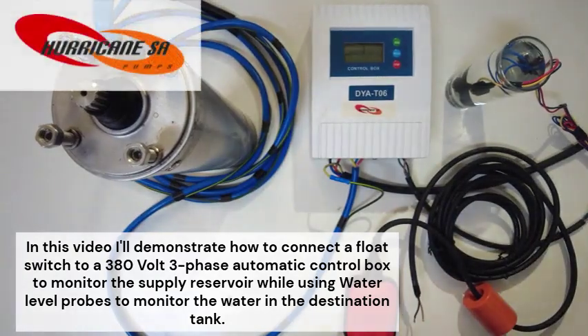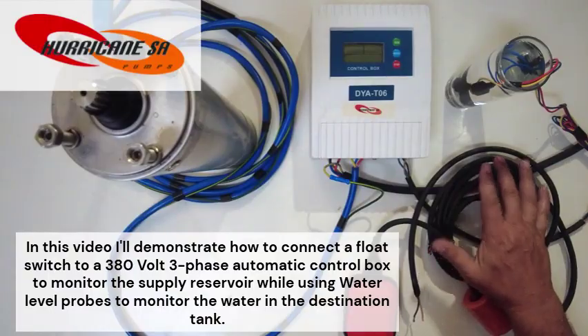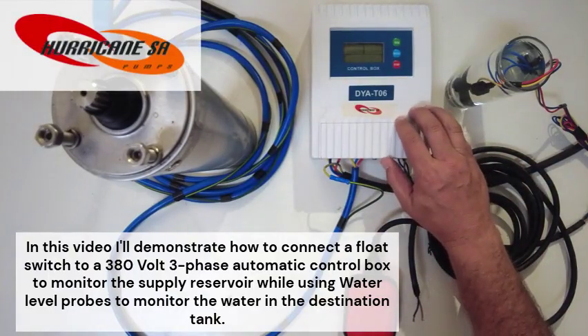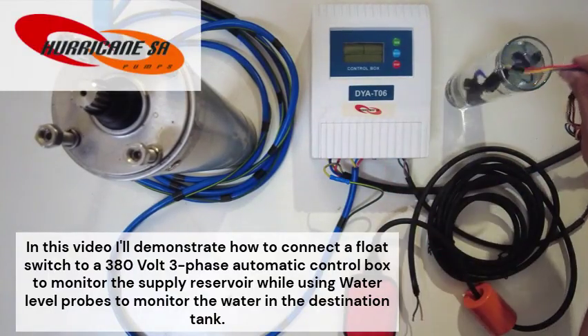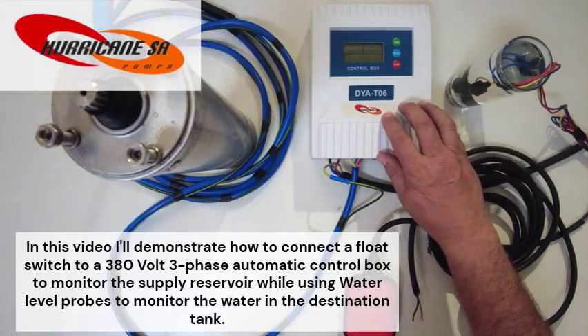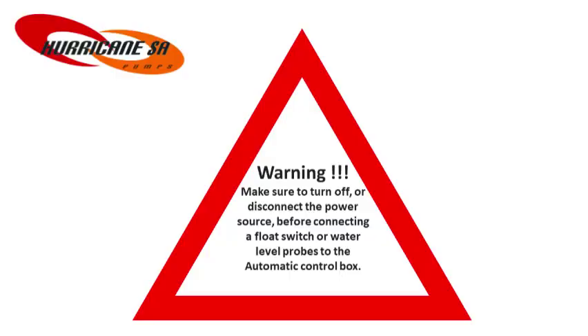In this video, I'll demonstrate how to connect a float switch to a 380-volt three-phase automatic control box to monitor the supply reservoir while using water level probes to monitor the water in the destination tank. Warning: make sure to turn off or disconnect the power source before connecting the water level probes into the automatic control box.